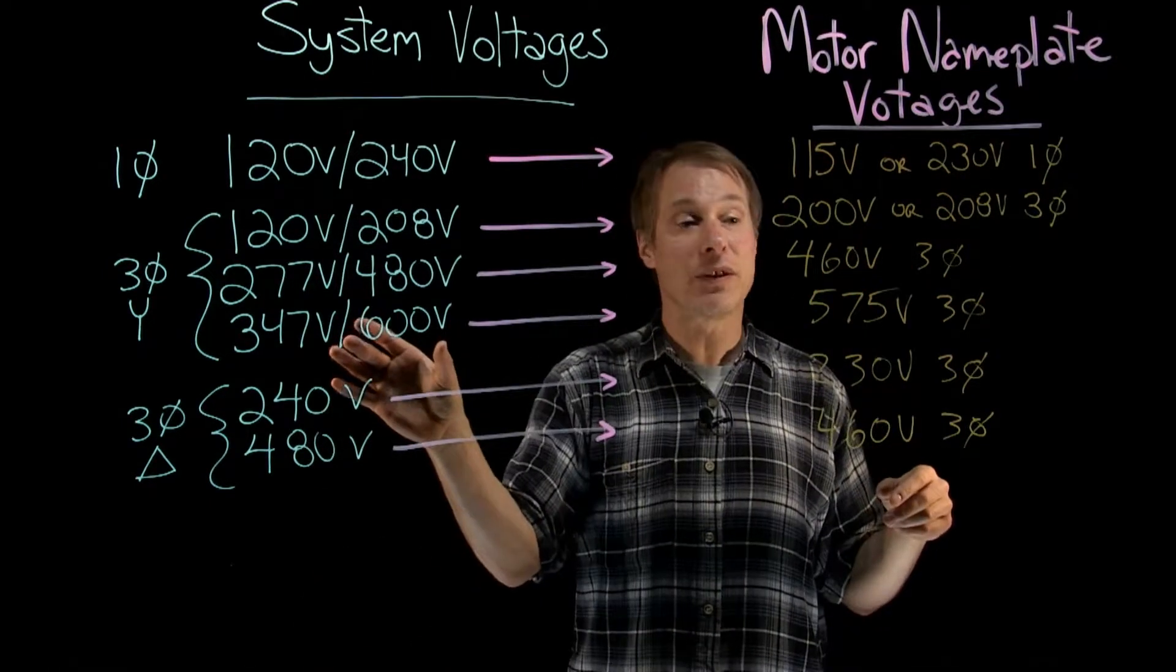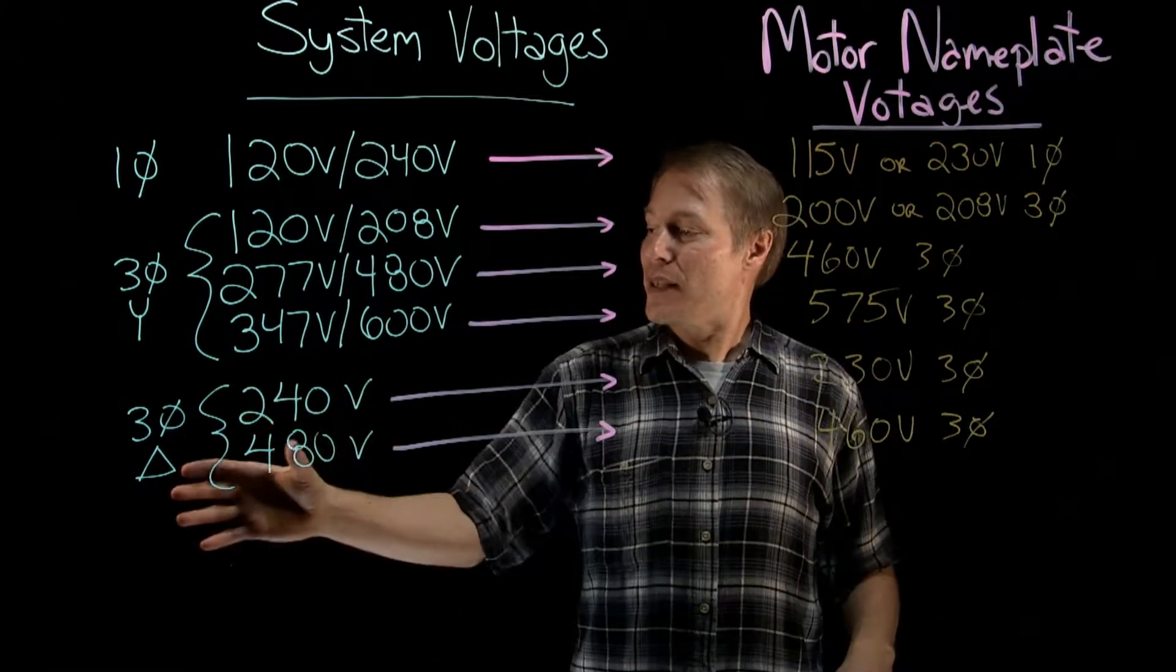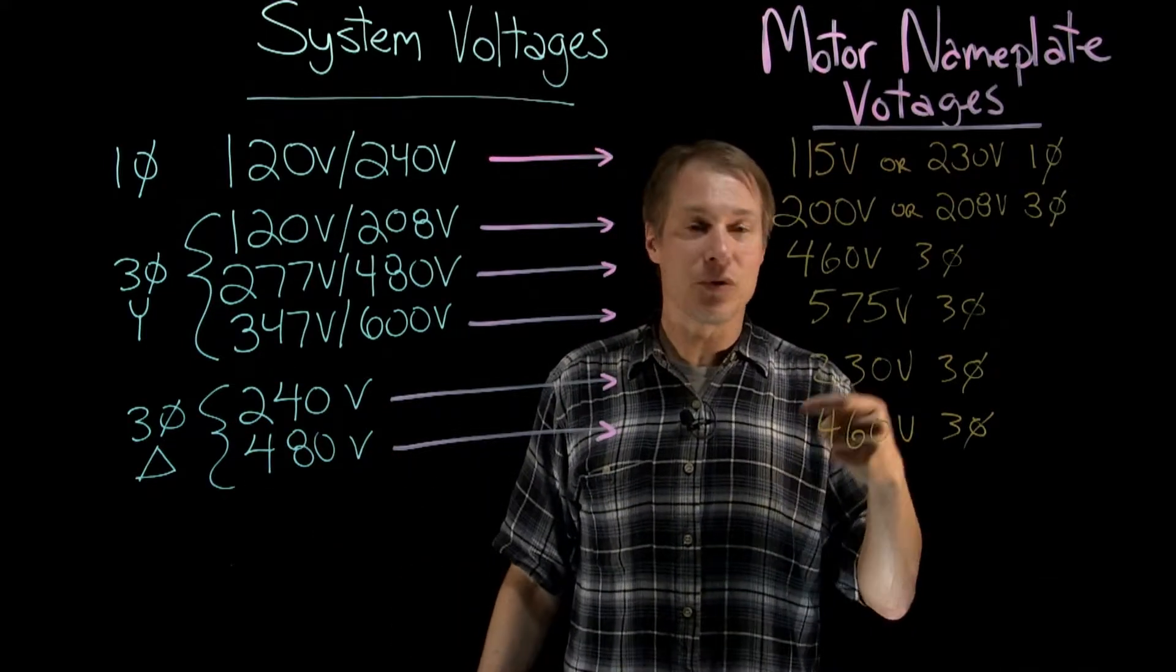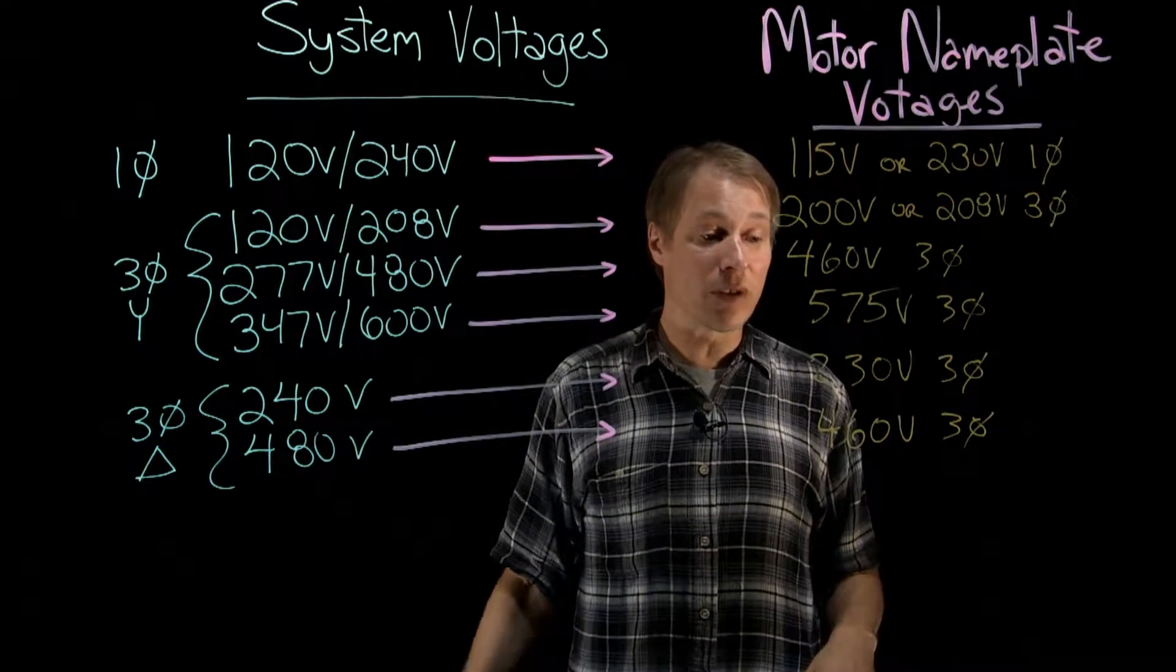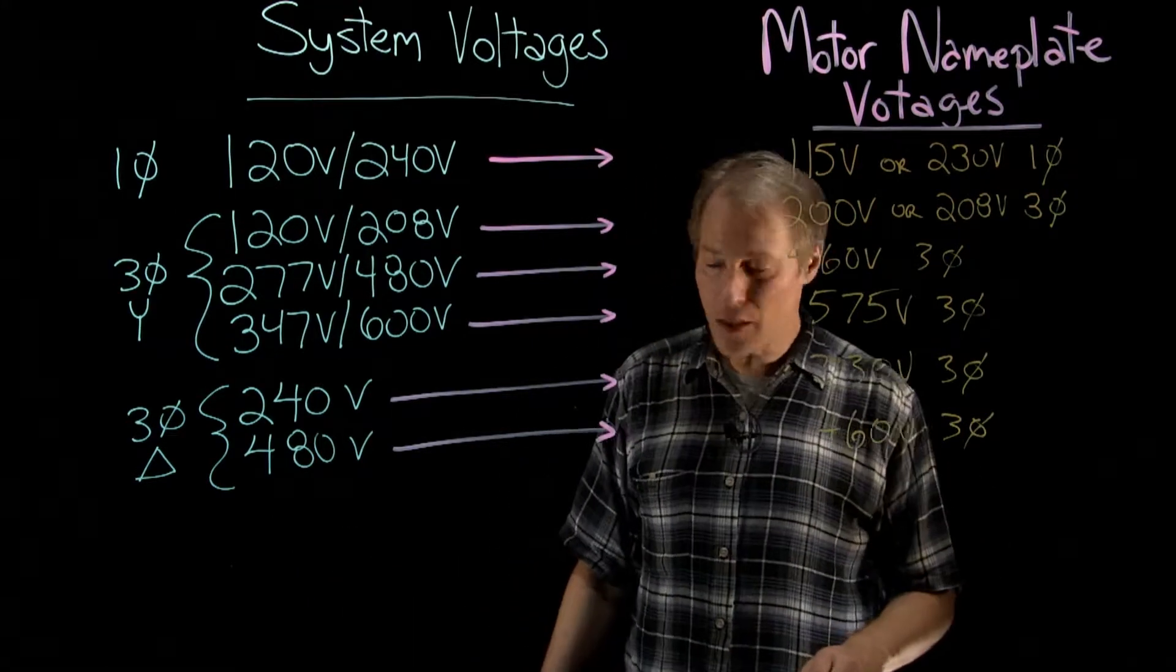And then for the delta systems, the 240V system would connect to a 230V three phase motor. And then the 480V would connect to the 460V three phase motor.